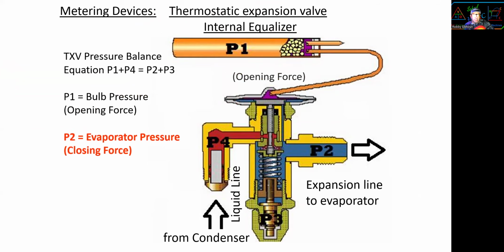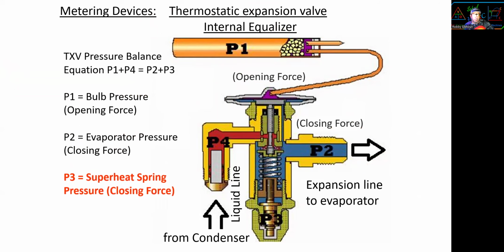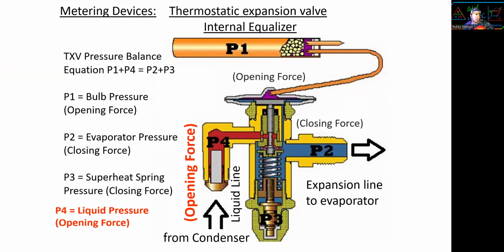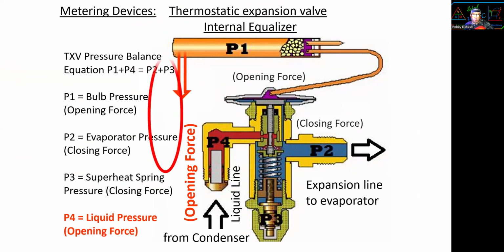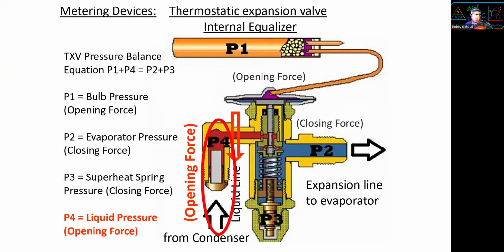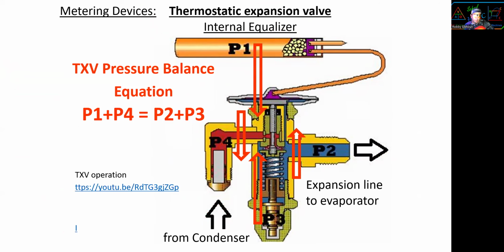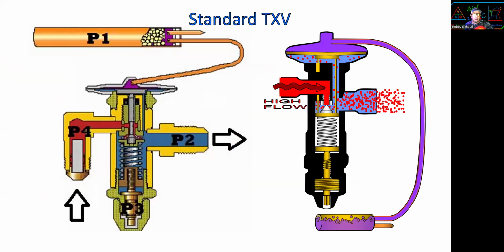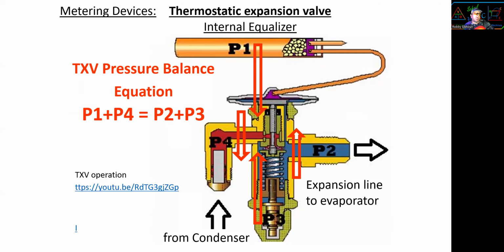Pressure number 2 is the evaporator pressure. That's your closing force. Pressure number 3 is also a closing force, your superheat spring pressure. And the opening force is condenser pressure, liquid pressure from the condenser, high side pressure. That's your opening force. Alrighty, there they are. There's a video on TXV operation.